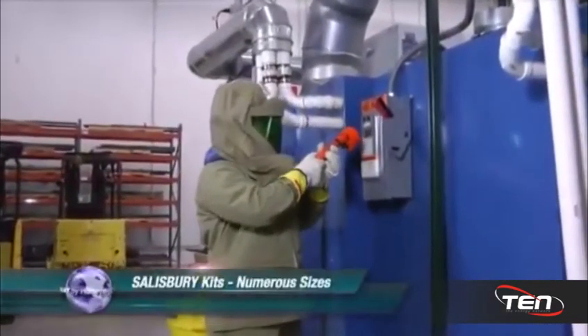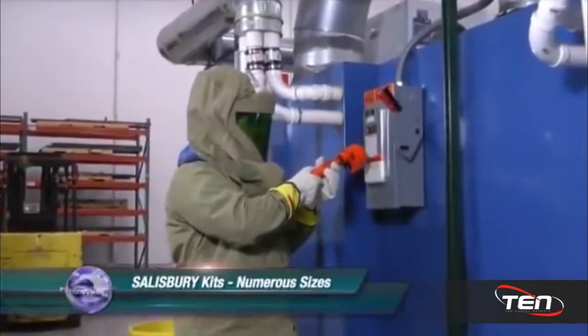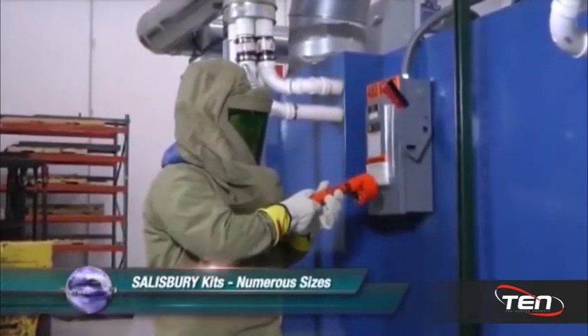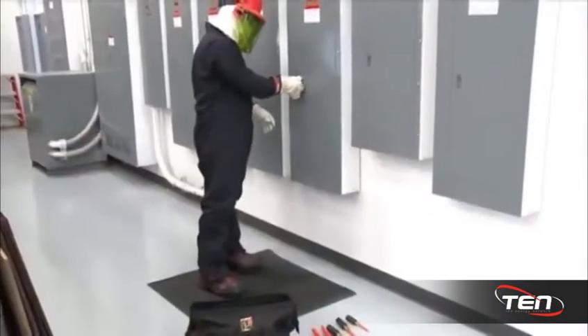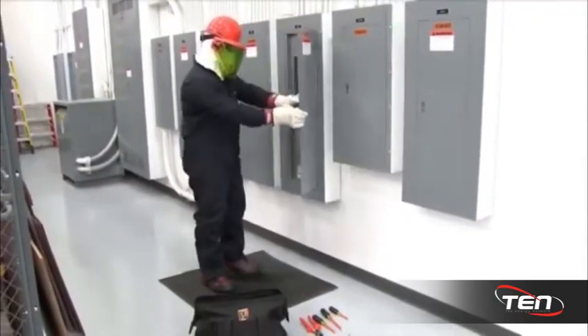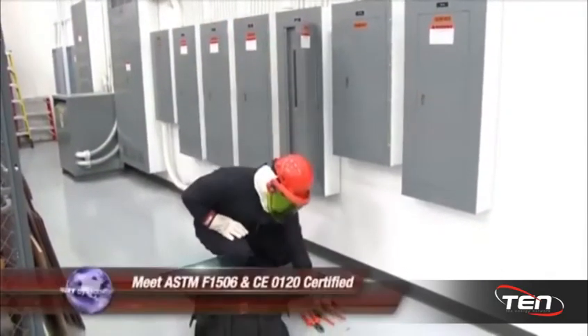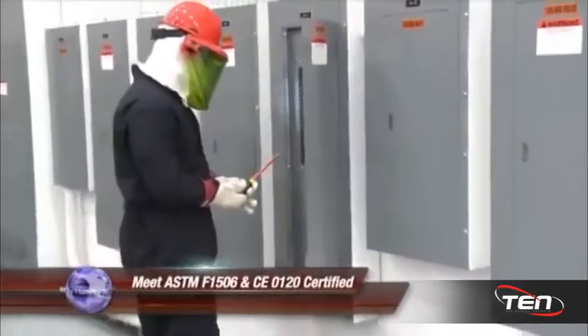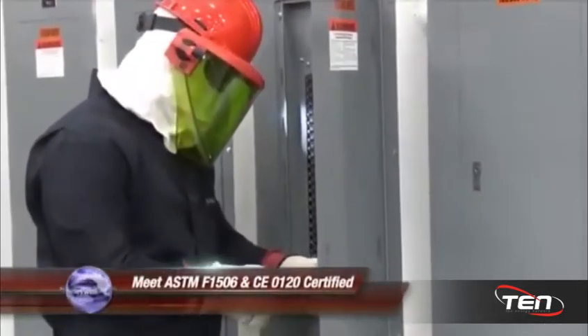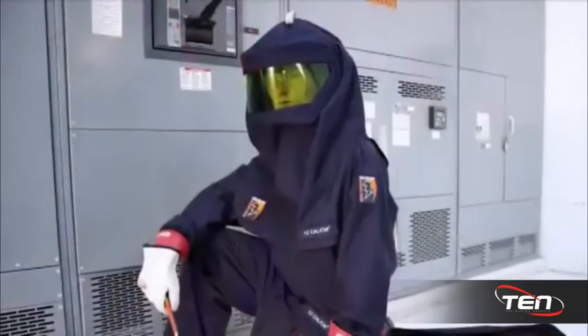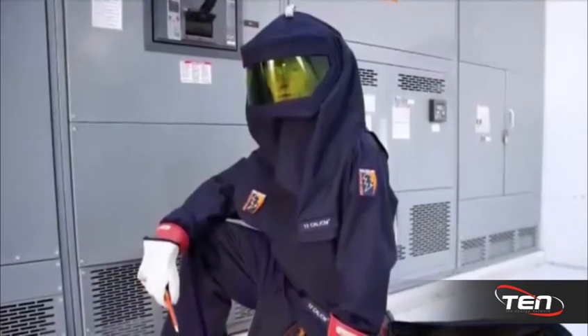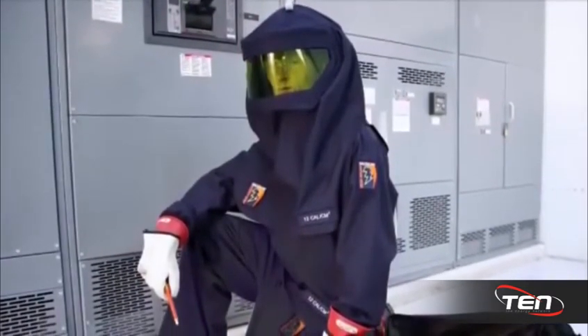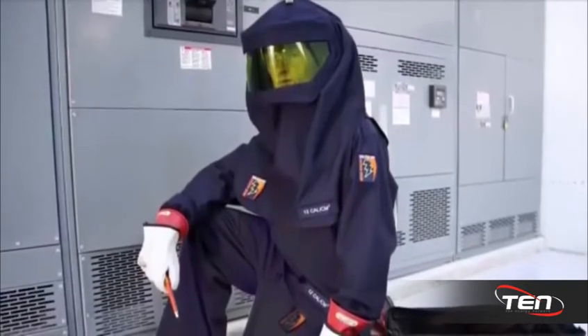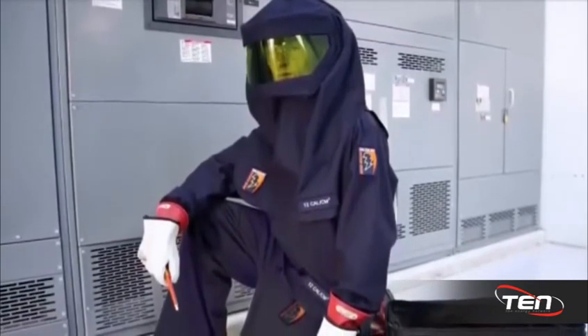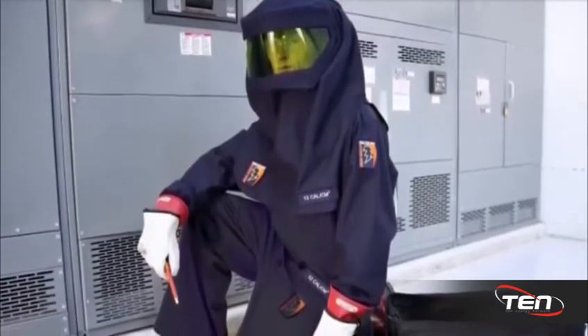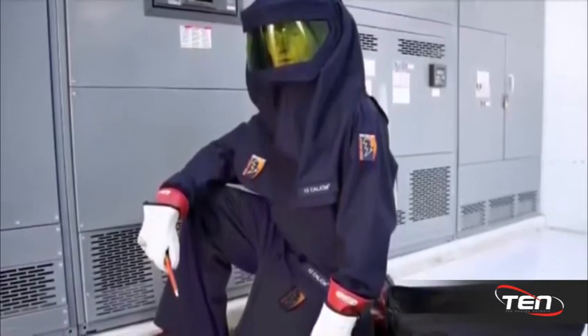All garment kits are available in numerous sizes and include specialized storage bags to keep the gear protected when not in use. All of Salisbury by Honeywell's garments fit comfortably over a worker's clothing, meeting ASTM F1506 standards and are CE 0120 certified. Another option to meet NFPA 70E Hazard Risk Category 2 requirements includes a switching hood, arc-rated coat, and arc-rated overalls along with proper safety glasses, hearing protection, gloves, and footwear.